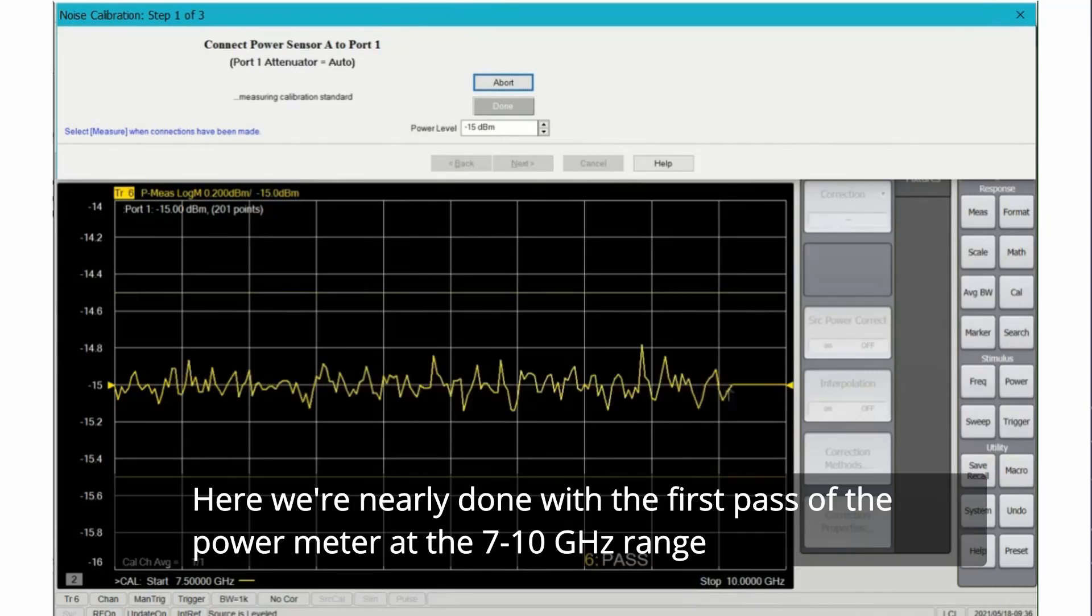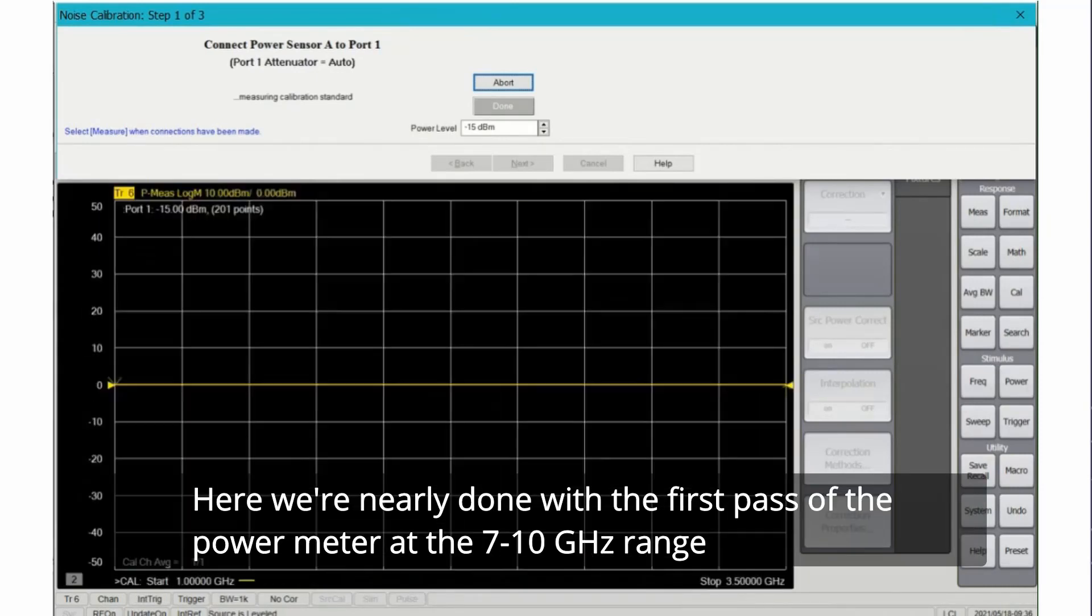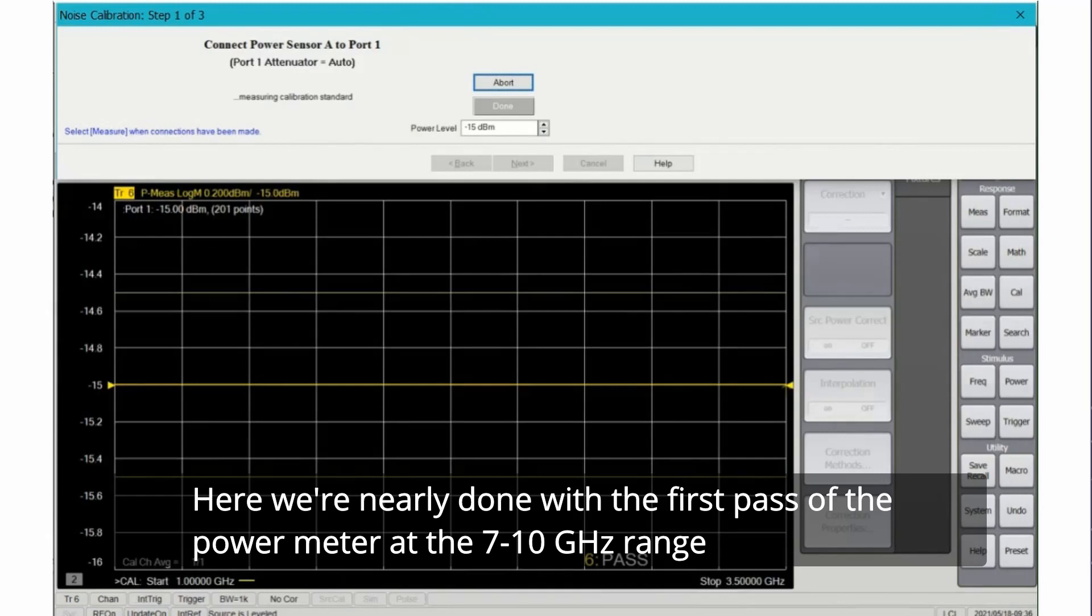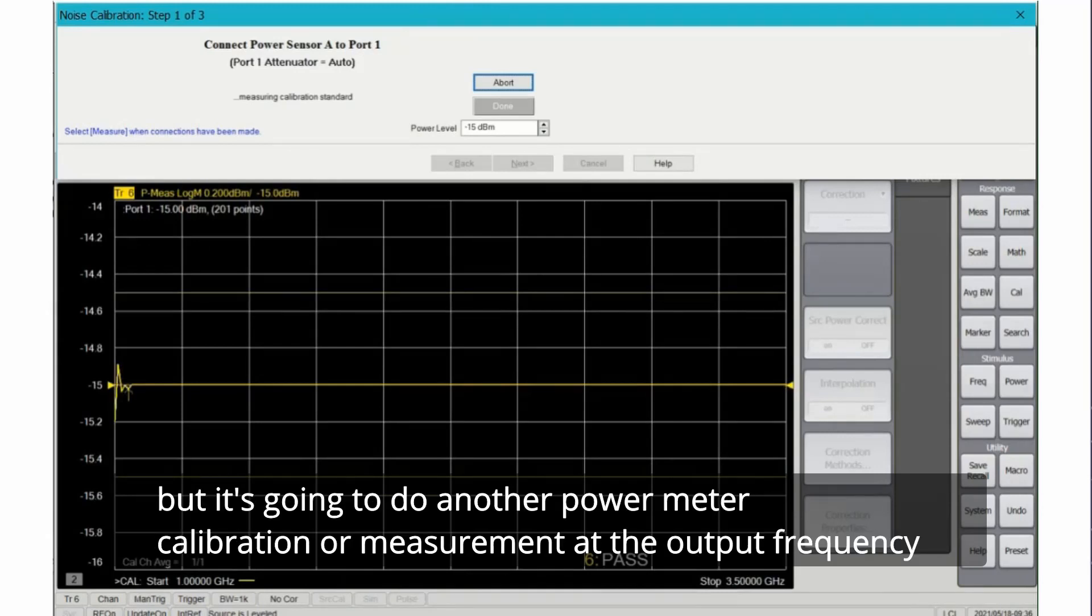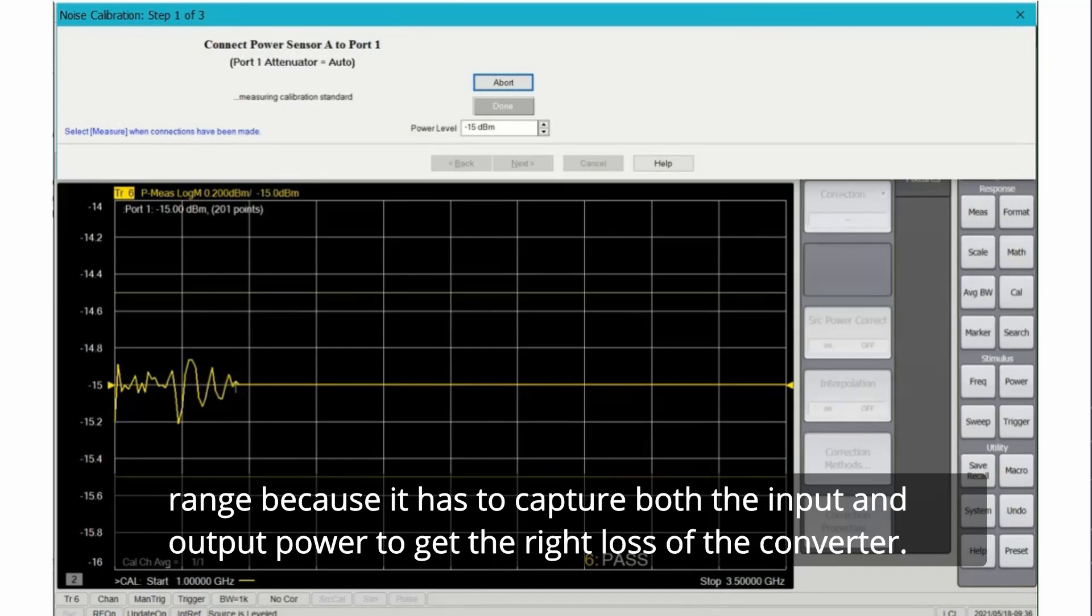Here we're nearly done with the first pass of the power meter at the 7 to 10 gigahertz range, but it's going to do another power meter calibration or measurement at the output frequency range because it has to capture both the input and output power to get the right loss of the converter.